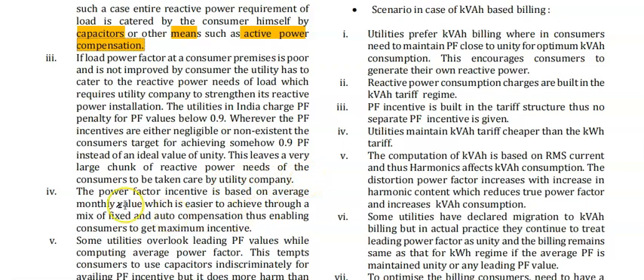That's the thing. Fourth point, the power factor incentive is based on the average monthly value, which is easier to achieve through a mix of fixed and automatic compensation, enabling the consumer to get maximum incentives. In this case, we can get maximum incentives. Some utilities overlook leading power factor values while computing the average power factor. Here, if we are calculating the power factor for the whole month, at some point of time we can get a leading power factor.